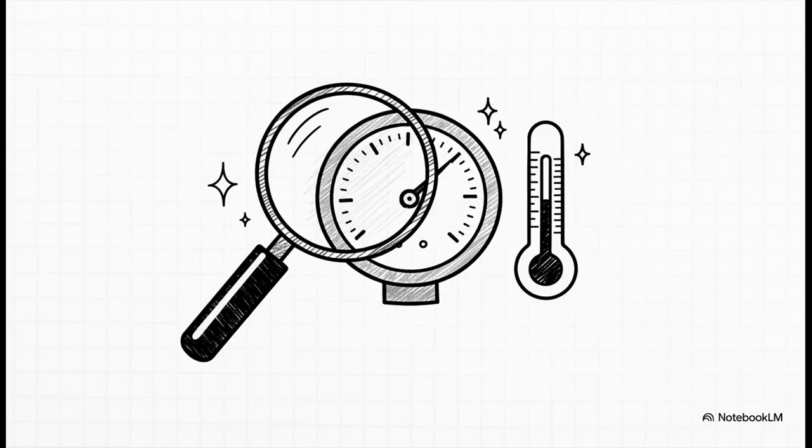And here's the simplest way to remember it. The measurement is accurate. That's the whole shebang. Calibration is entirely about securing accurate data. It has nothing to do with the overall process flow. And it's not about how the machine was installed. It's strictly asking, is this thermometer telling me the true temperature? Is this pressure gauge giving me the exact PSI?